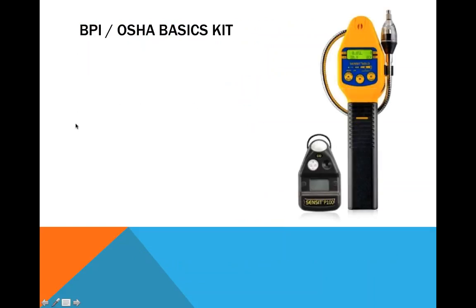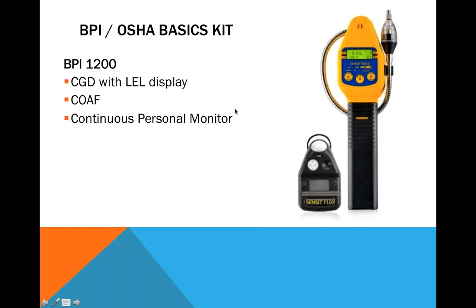We also put together a kit to cover both the BPI and OSHA concerns. That's the device I just mentioned, the combination device. And what's required in BPI 1200 very basically is a combustible gas detector with LEL display, a device that measures CO air free, and a continuous personal monitor. And the BPI has clarified the standard in that the continuous monitor for CO must be on all the time and it can't be part of another device. It has to be a separate device.